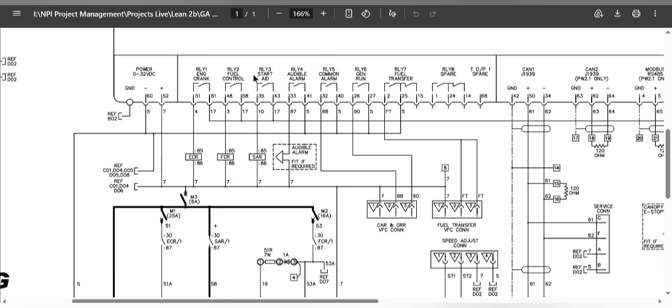After that, as you can see, the starting aid relay will start the starting aid when you start cranking the generator. This will keep the glow plugs turned on and keep the fuel transfer pump turned on, to properly fuel up the fuel pump and fuel injection system. After that the glow plugs run for a certain amount of time, and then finally the starting aid is in and cranking the engine over, and the engine starts successfully.